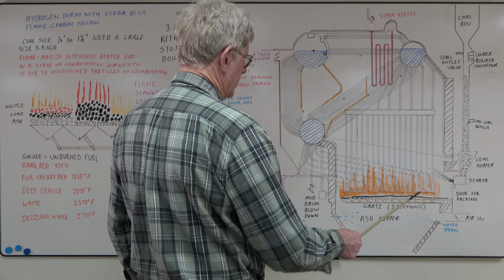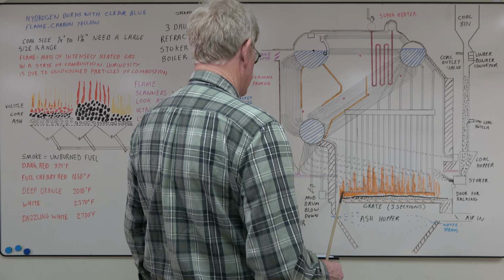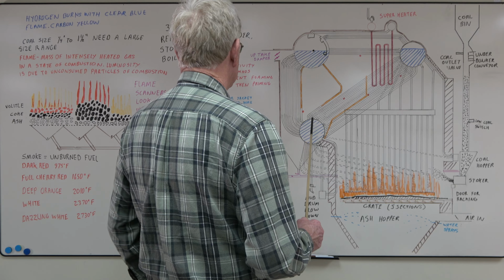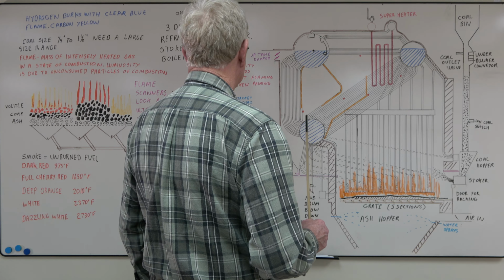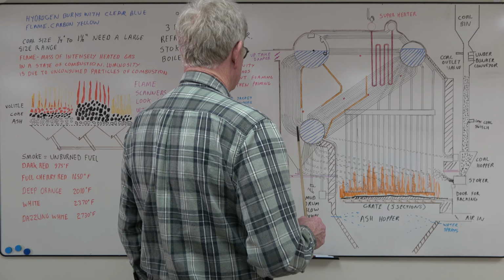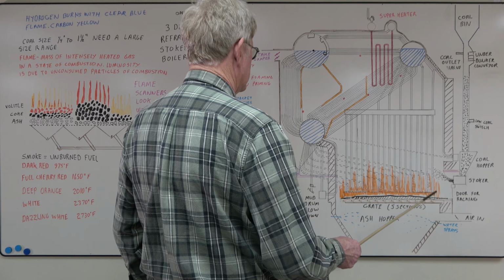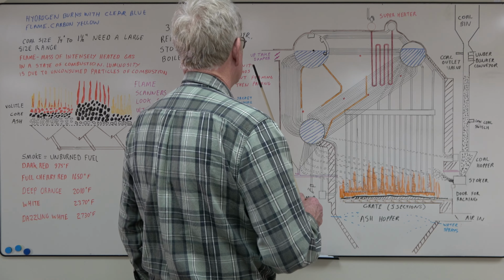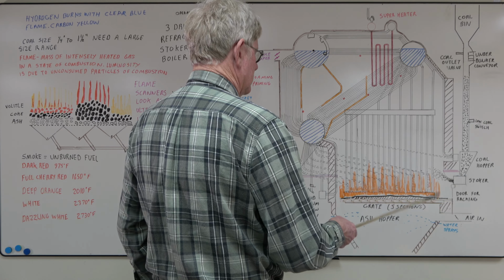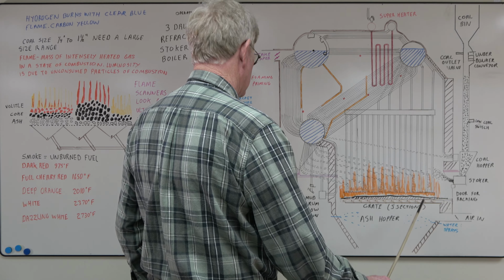You never did blow the water walls, because you started these walls with water, you could damage the tubes pretty quickly. And I really didn't have a problem with the chemistry. This one ran with soft water, and we had a compound to keep the suspended solids in solution so they really didn't drop out. Other than that, it's mostly just play with the stokers, keep a good even fuel bed, and dump it.